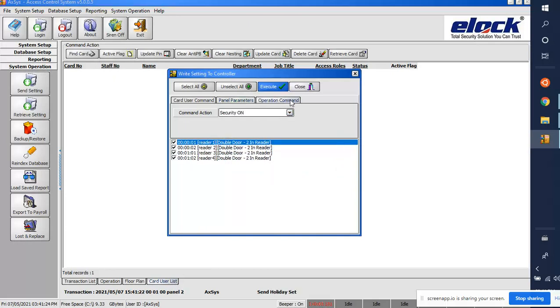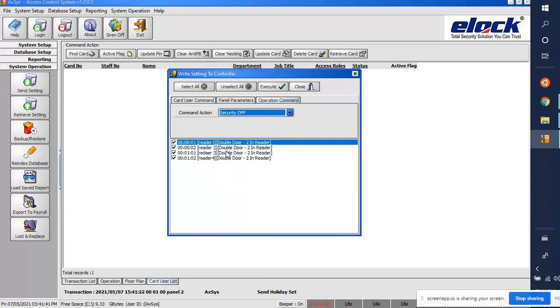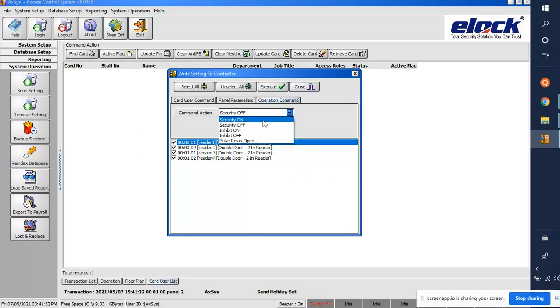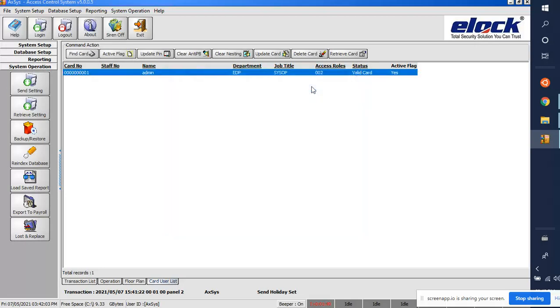The next step is 'Operation Command' — execute it. For example, if you want to open all doors, go to Security, click 'Security Off', select all panels and readers, and execute. All doors will open automatically. When you click 'Security On', all doors will close and will only open when a card is shown on the reader. Click OK.